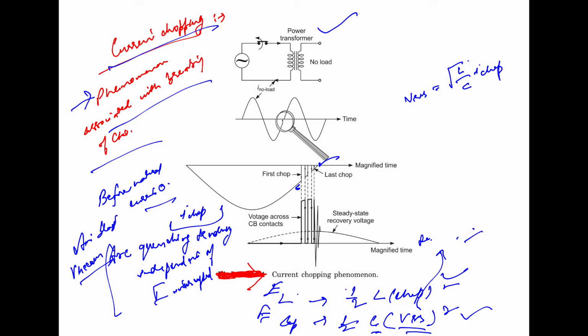We get that the higher the value of the current at which it gets chopped, the more will be the restriking voltage, and higher will be the possibility of the breaker not being able to withstand it and breaking down subsequently, which is obvious from this diagram. That is what we get from this expression and from this diagram: the higher the value of the current at which it gets chopped, the more the restriking voltage, and the higher the possibility of the breaker breaking down subsequently.